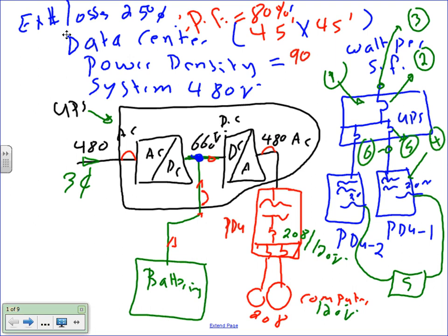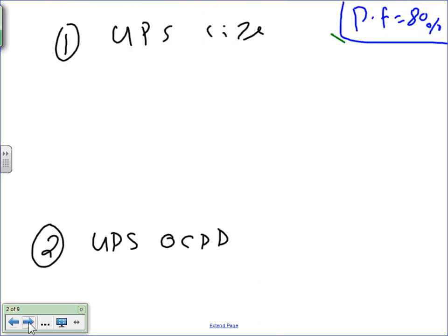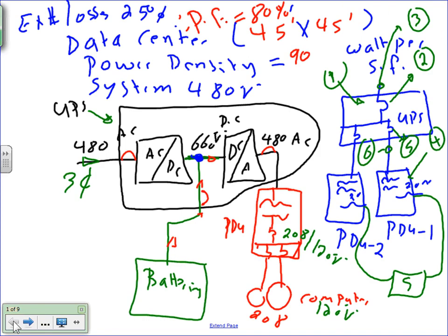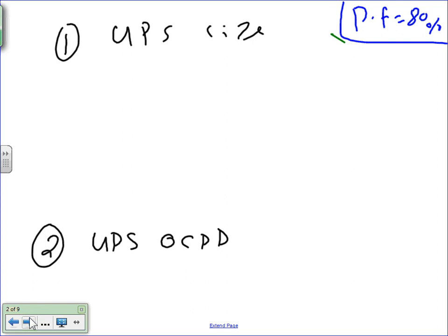Let's go size. Okay, so, I'm sorry. Yes, the supply, that's why we have a transformer. Typically, this is very typical, Chris. Typically, that side will be 208, 120. I'm not aware of any site where you feed the servers themselves at 480 in the US. I'm sure somewhere else in the world they feed them at 230. But I've never heard or seen a server fed at 480. Yeah, or 277.